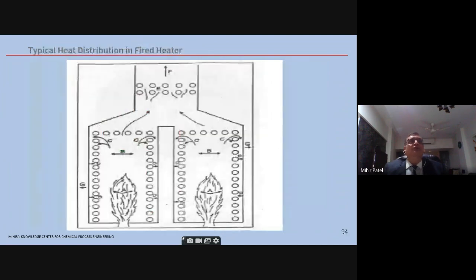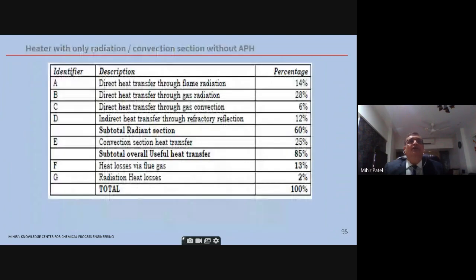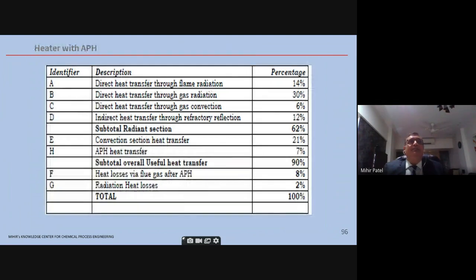Now I want to show you the typical heat distribution in a fire heater. So here you will see a fire heater which doesn't have an air preheater, APH. If you can see, the radiant section is about 60%. So 60% efficiency is obtained in the radiant section. If you don't have a convection section or APH, you will get only 60% efficiency. If you add the convection section, you get 25% more, which is 85%. You still lose 15% energy. Now, if you add an APH, you are gaining that 5%. So you get 90% efficiency of the overall heater. Nowadays, heaters can go up to 93% also, depending on the vendor. But a balanced draft heater will give you 90% where the APH is there.